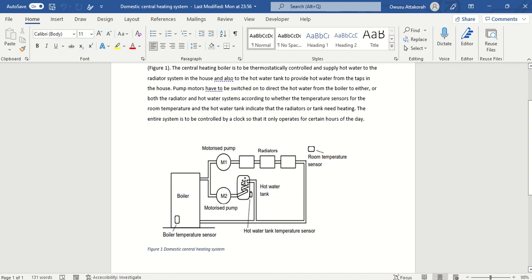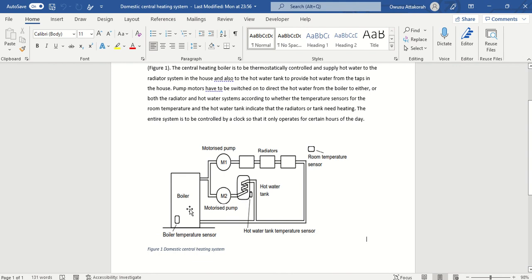This boiler system has three inputs: the room temperature sensor (sensor one), the water tank temperature sensor (sensor two), and the boiler temperature sensor (sensor three). We have three outputs: motor M1, motor M2, and the boiler heating coils. In the program I would add one more input - a manual start switch - making four inputs, and one more output - an internal relay.